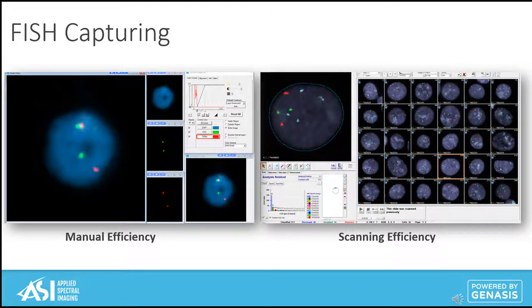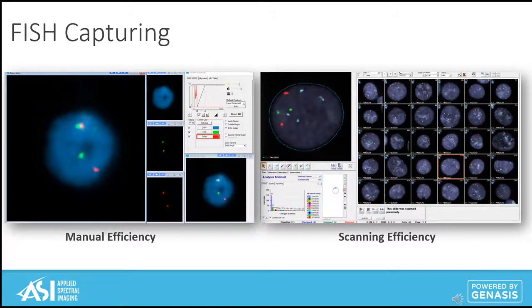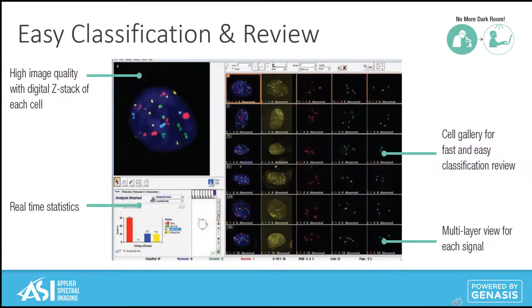SpotScan is an efficient scanning algorithm for both metaphase and interphase imaging. The system first detects dense areas on the slide during a 10x scan, then relocates back to these cells with either 60x for interphase cells or 100x for metaphase cells, capturing the images with their predetermined filters. Our algorithm is designed to detect and score thousands of cells, providing consistent, standardized, reliable results. During review and analysis from the comfort outside of the darkroom, technologists are able to view a high-quality digital Z-stack image for each cell, multiple-layer display, and signal detection for easy classification with real-time statistics.